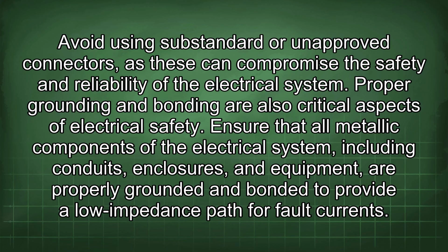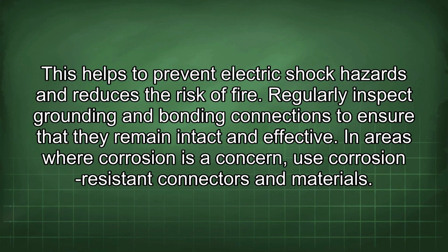Proper grounding and bonding are also critical aspects of electrical safety. Ensure that all metallic components of the electrical system, including conduits, enclosures, and equipment, are properly grounded and bonded to provide a low impedance path for fault currents. This helps to prevent electric shock hazards and reduces the risk of fire. Regularly inspect grounding and bonding connections to ensure that they remain intact and effective.